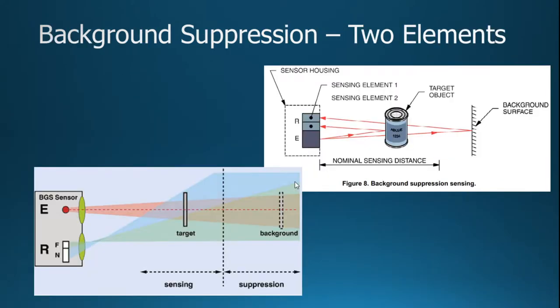So what is a background suppression sensor? How does it work? Well, it has an emitter and that emitter emits and shines against the background surface. And then if some target comes in, what happens is there's actually two sensing sensors. And what it allows us to use is kind of triangulate between those to determine whether or not there's something in the path, rather than just trying to check the target in front of it. The other thing about this is because it's comparing the background with the foreground, it's less likely to be tripped by just random light that may be coming, some sunlight that might be coming into that frequency. So it's looking for the background surface and it knows what the background is, so the sun coming back is not going to trigger it. It's just looking for the difference between what it is expecting at that maximum and that target range there.